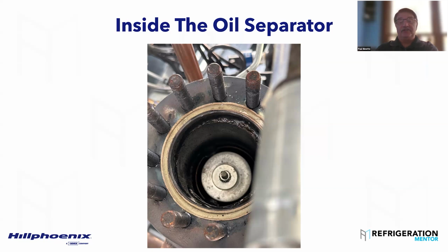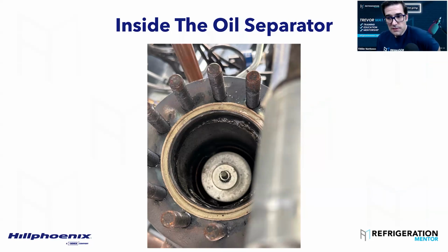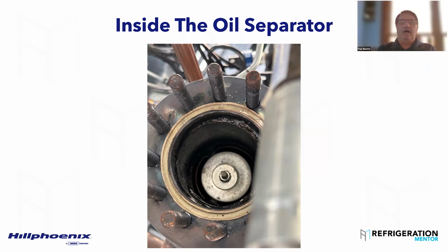25 psi will blow that filter out. Unlike a Temprite, where you blow out the bottom O-ring, with a Westemeier, the way it's seated, it's going to blow the actual filter material out. And that becomes a nightmare you don't want to deal with. Yeah, because now all the metal and stuff is in your oil lines and in your oil filters and could get in your components. When it blows out, is there a pressure differential across it? What will you see? If they go check, should it be zero across it? I tell everybody, you should have a minimum of 1 to a maximum of 12. If you have 0, you need to calibrate your gauges, or you need to look at that filter because it probably blew out on you.